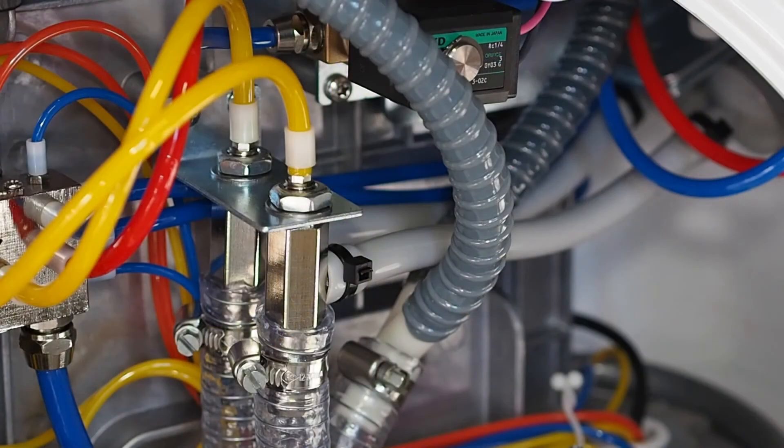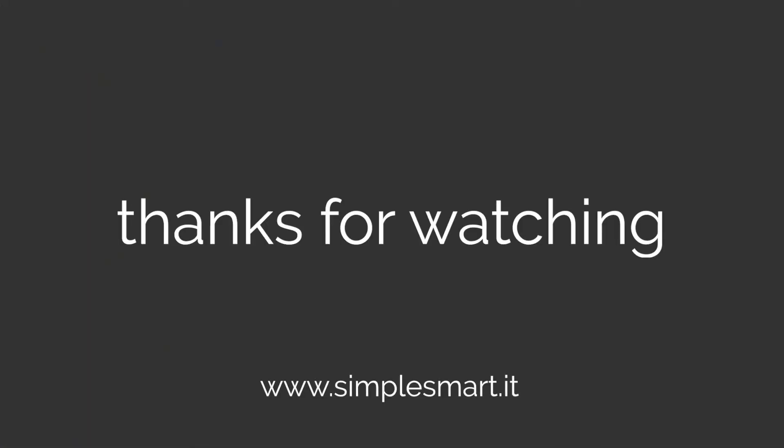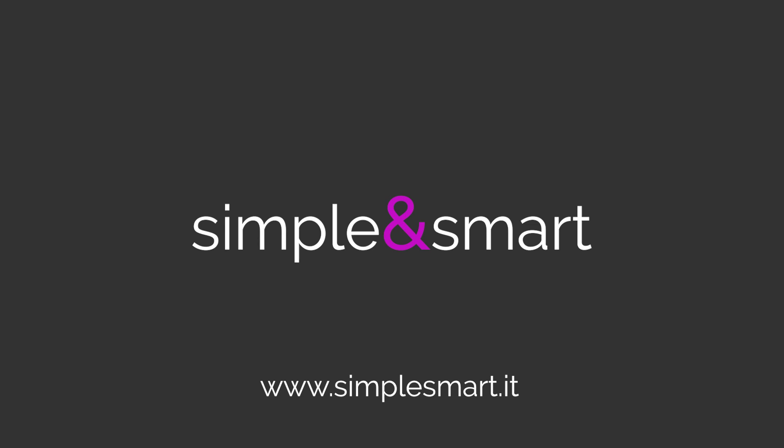The problem could be the Venturi valve, but this is really rare. We recommend using a bigger compressor for a dental unit with two Venturi air valves. It needs more air. Thanks for watching. Be simple, be smart.